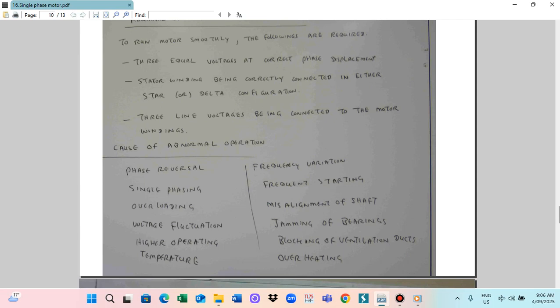Sometimes even the supply wire blows out because they bypass the starting switch, so the motor draws a higher current. Initially the motor winding is weaker, so it draws the higher current. Since they bypass the starting relay, the motor draws high current. Even an electric fire can happen. But here, if you are an electrician and do like this, people will complain and your license will be affected. But in our country, no problem. You can do anything, no problem.